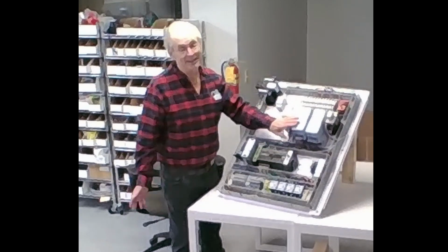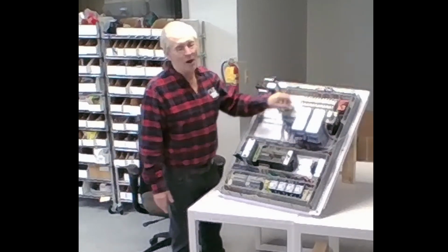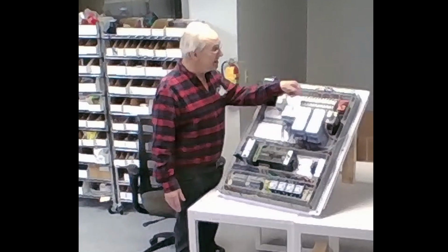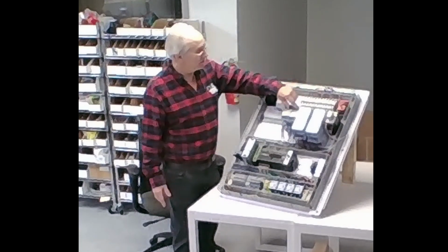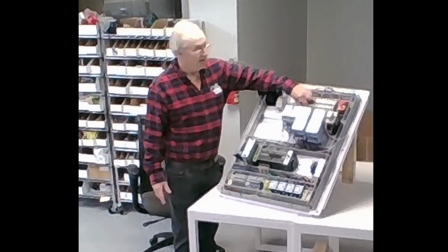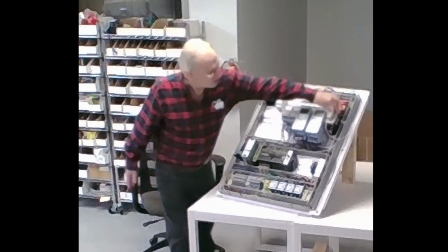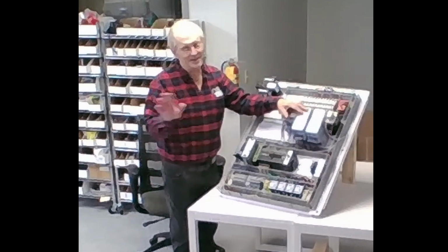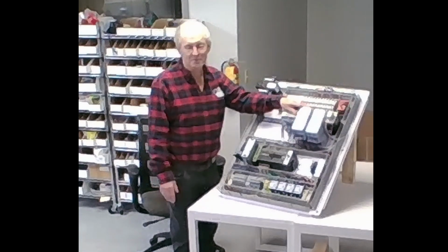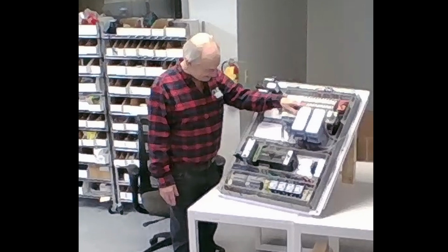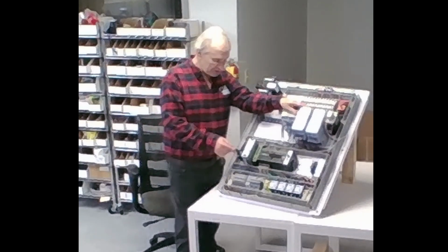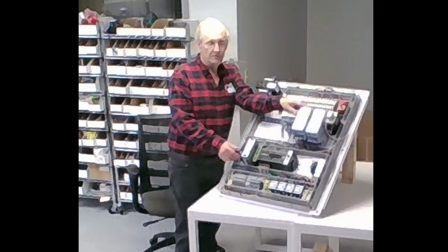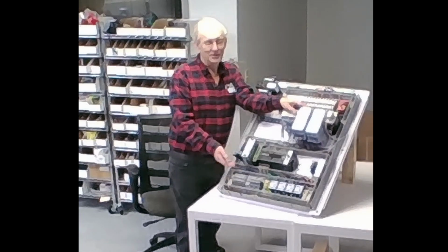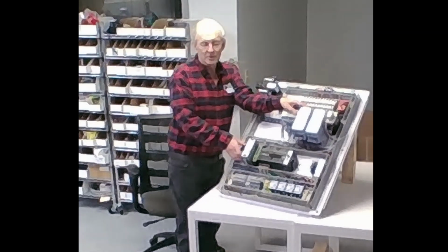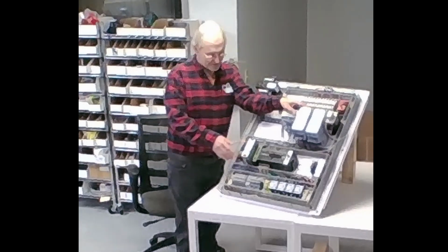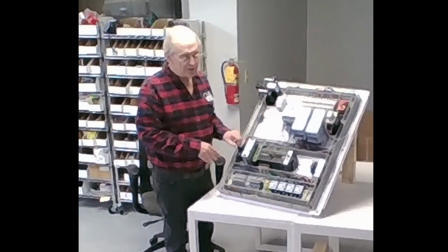And it's actually a pain because it means you have to loop the wires around the thing. Whereas it's really easy when these two here are coming right off the breaker, and I don't have to go all the way out around and come back up. Why they did that, I have no idea, but that's the way VFDs are in the world. Anyway, the point about the fuses is that you want the fuse to fall down out of the connection. So when I see a fuse holder that's flipped the other way, that's no good.